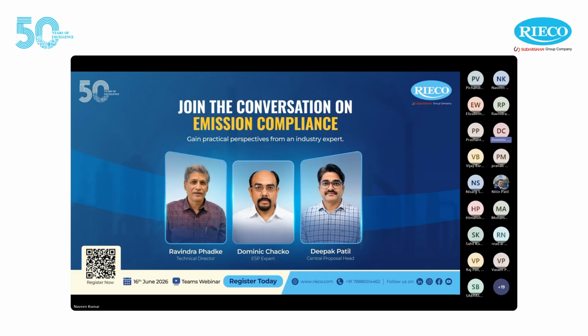False air leakages into ESPs can lead to mainly two types of issues, or three types of issues, I would say. One is that if the false air leakage is sufficiently high, it simply adds to the gas flow which the ESP treats. That means an ESP that is designed for, say, X meter cube per hour of gas may have to treat 1.15x or 1.5x of gas flow if the leakage is of that order, 10% or 15%. And it is not very rare. I have seen in many places that these leakages can be as high as that if some important issues are not properly addressed.